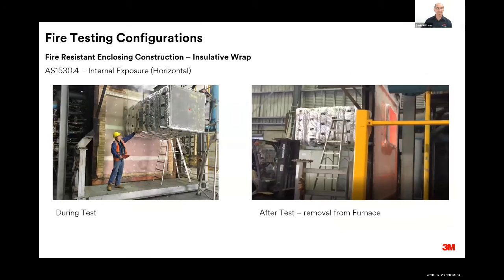So testing configurations, just to show you some pictures of how we test fire-resistant enclosing construction. First picture here, this is showing the testing of a horizontal duct for internal exposure. And see that the lab technician has his hand on the duct, and yet you can see at the end of that duct it's red hot inside. So that's the duct wrap providing insulation to protect from heat getting outside of the duct.